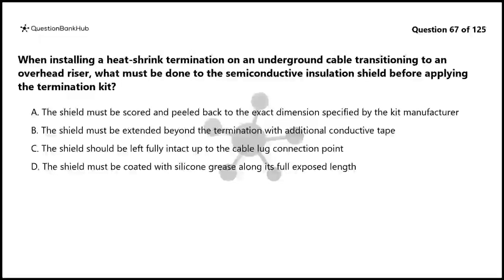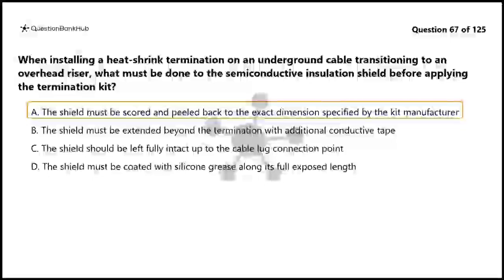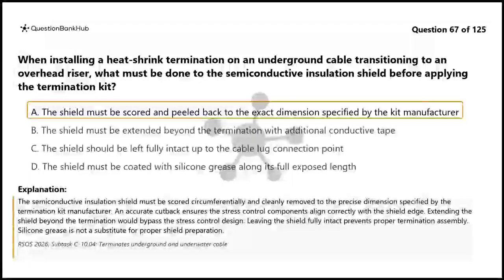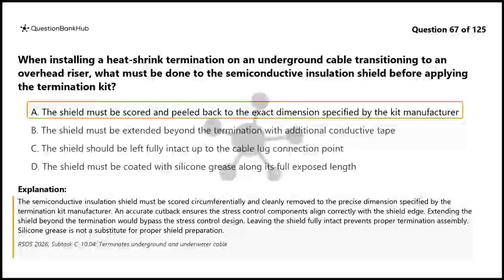The correct answer is A. The semiconductive insulation shield must be scored circumferentially and cleanly removed to the precise dimension specified by the termination kit manufacturer. An accurate cutback ensures the stress control components align correctly with the shield edge.